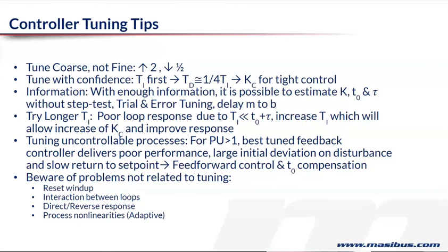Or when you are doing some trial and error, just fiddling with your controller, you've changed your P band. Now you will see that there is some delay from the time you change your set point or you change the output MV, to the time the process responds to it. So with your watch or a timer, you can figure out it took, let's say, 30 seconds by the time the process started responding. So actually you have captured the dead time. All right.